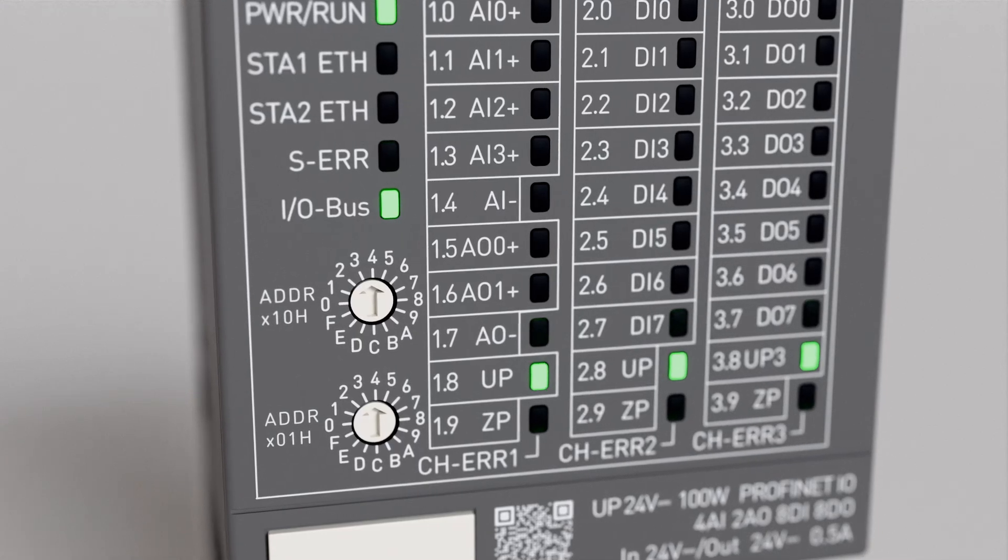At this point you might ask, but what if we set station name by rotary switches and then send settings through IP configuration tool? I'm glad you've asked. The thing is that CI501 station will take settings from IP configuration tool only if two rotary switches are set to zero. In all other cases, naming scheme with rotary switches will have priority.